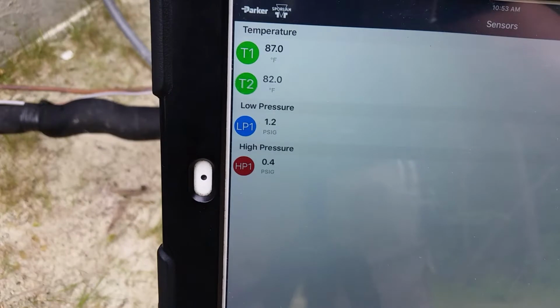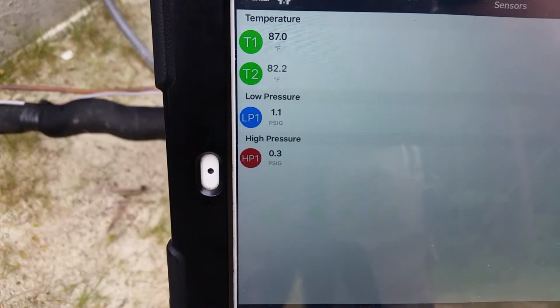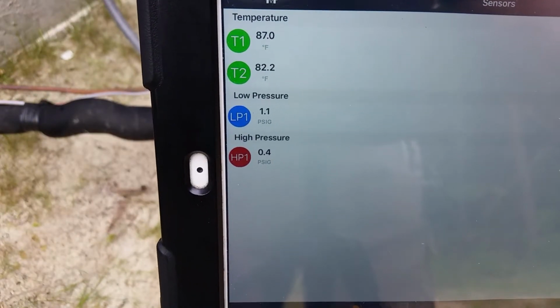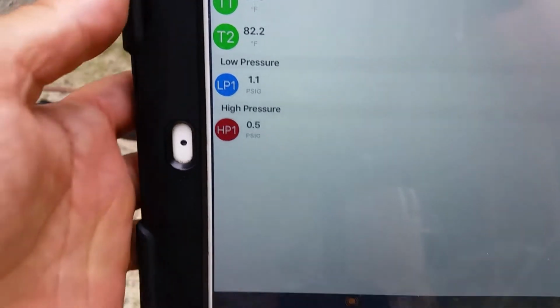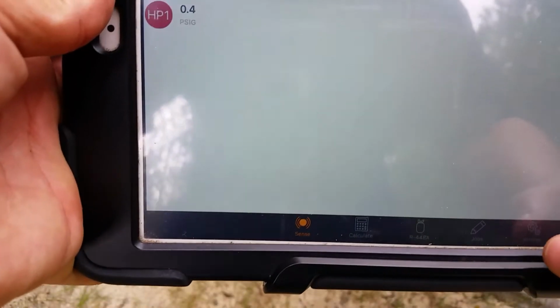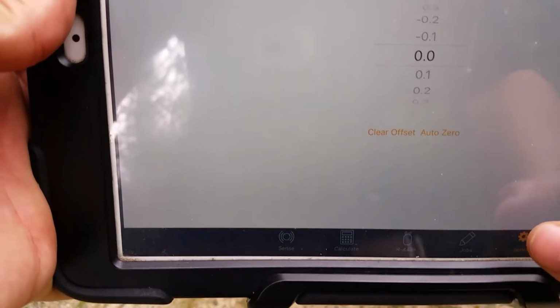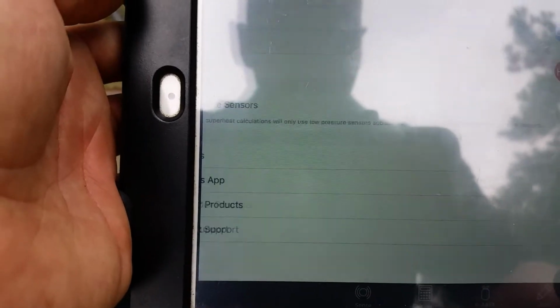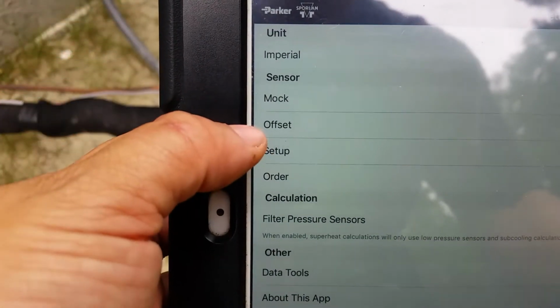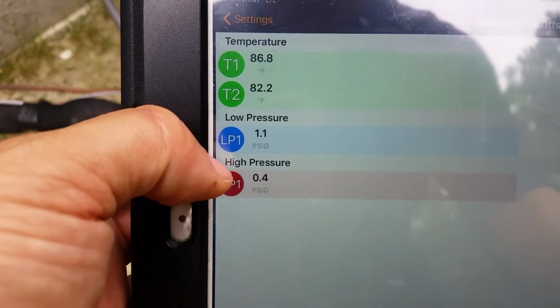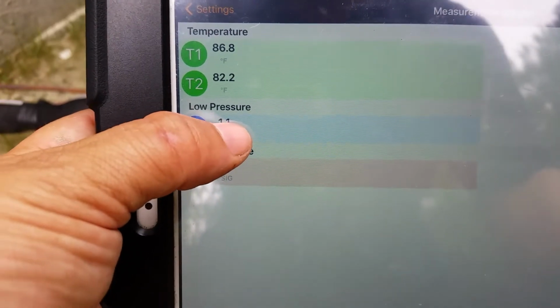Alright, so we're over at the condenser now. Got all our probes are reading. And as you can see, our 2 pressure transducers are not zeroed. So we're going to go ahead and go to our settings. And you can see, let me back out real quick. When you go to the settings, there is an offset icon. You can click that, and then you can pick which transducer is off.